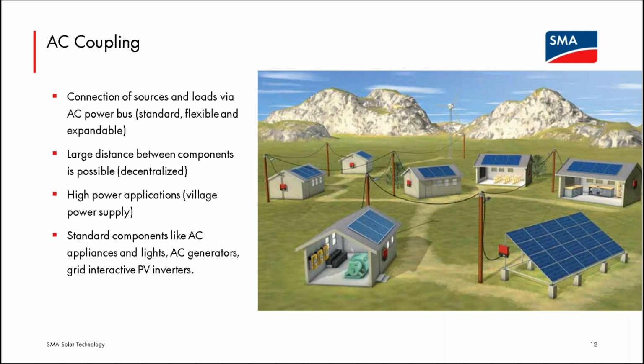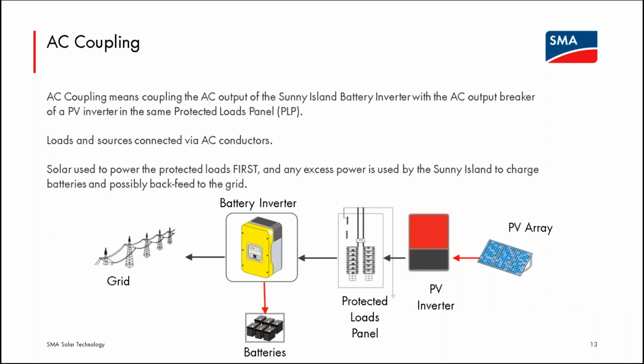So all of the AC power from the homes' PV systems, from their loads, all of this is connecting on the AC network across the power poles shown in this diagram. It is far easier to scale up and expand an AC network rather than DC. So it provides power more reasonably to remote, longer runs of wires, and it allows homes to use very readily accessible AC loads. So we really believe in this AC coupling. And as this device was built to be able to create and scale up utility quality grids, that's the whole reason for being for this device.